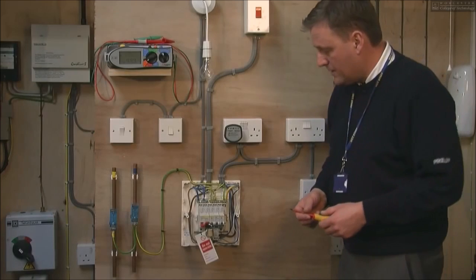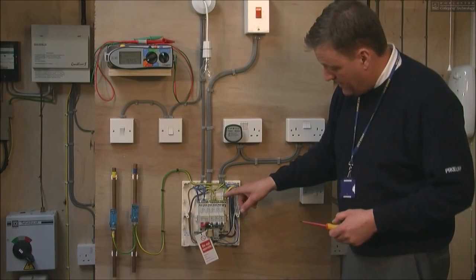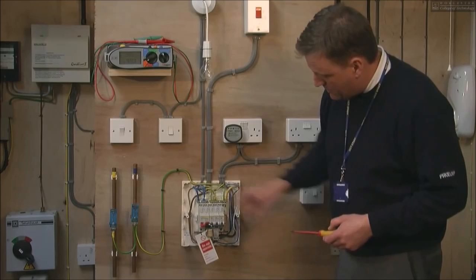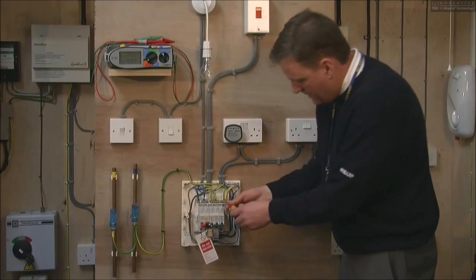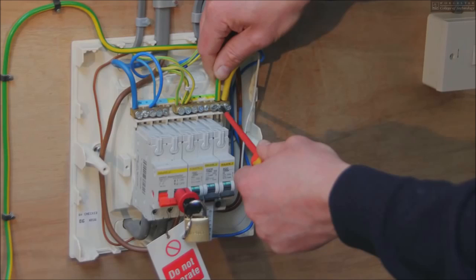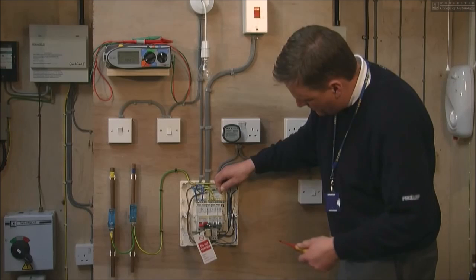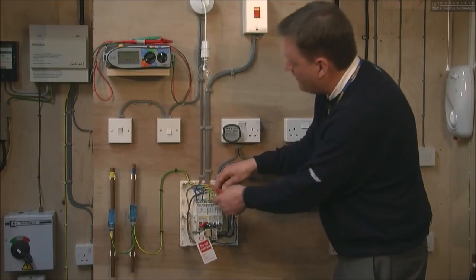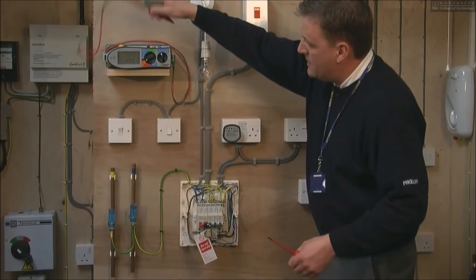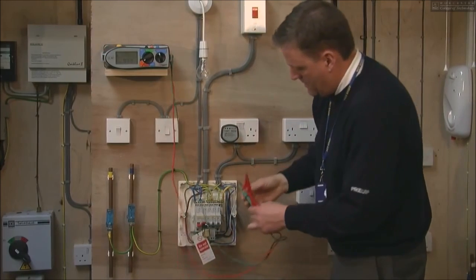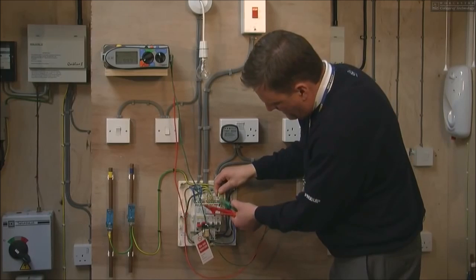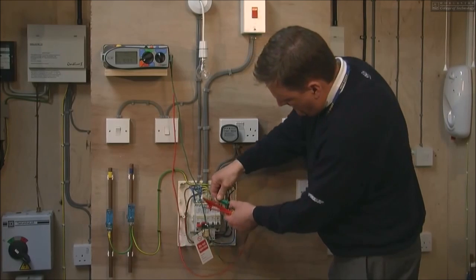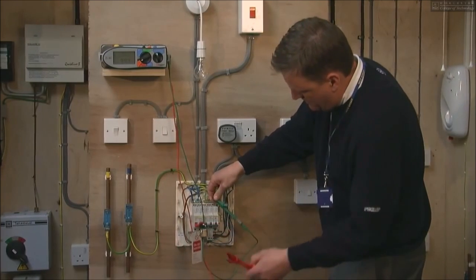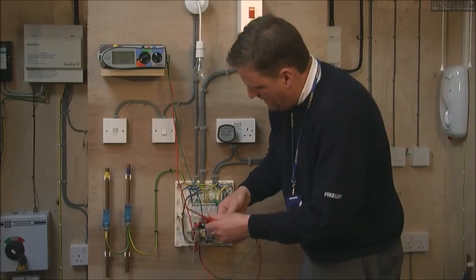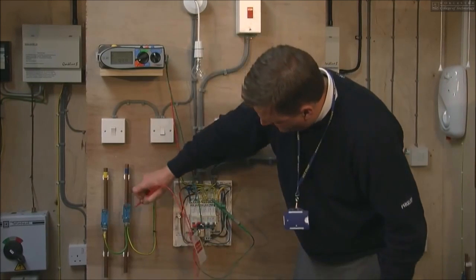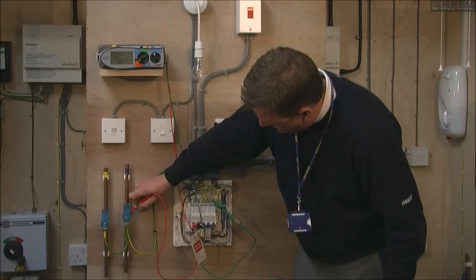One of the first tests we're going to do is we're going to check the continuity of the protective bonding conductor, which goes to the gas and the water. So we remove the conductor from the main earth terminal. We then take a test lead that we've zeroed.